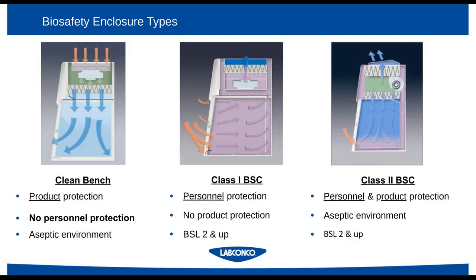So the last and perhaps most prevalent biosafety enclosure out there is what's known as a Class II Biosafety Cabinet or a Class II Enclosure. And these marry the principles of clean benches and Class I BSCs to produce both personnel and product protection. And that creates a safe environment that remains aseptic.